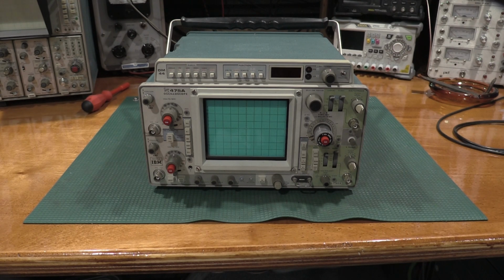So what will happen is the device under test, in this case a 400 series scope, will spin up and start drawing heavy current, which will cause the voltage to sag through the dim bulbs even more, to the point where it'll get down below its cutoff threshold and it'll actually start to sit there and kind of oscillate a little bit. That power supply oscillation is very hard on these units.